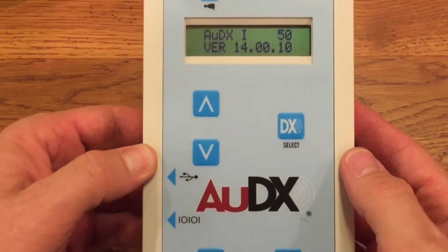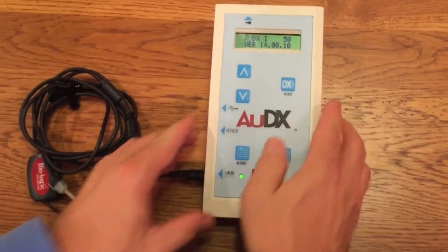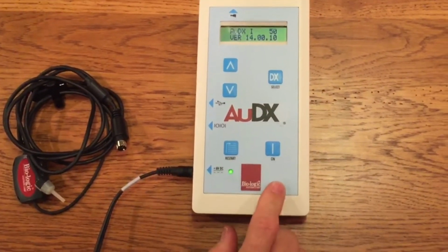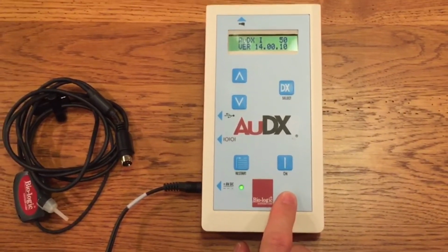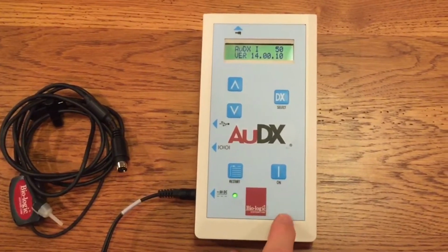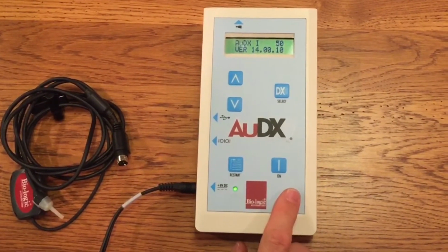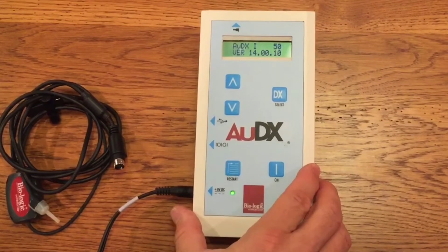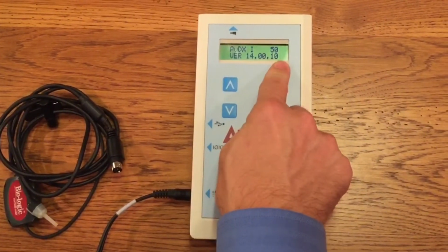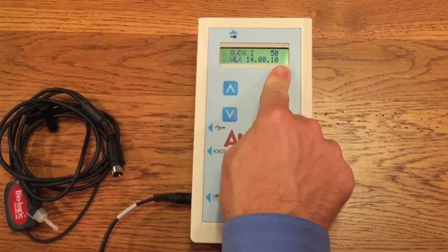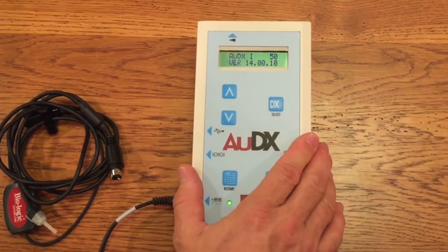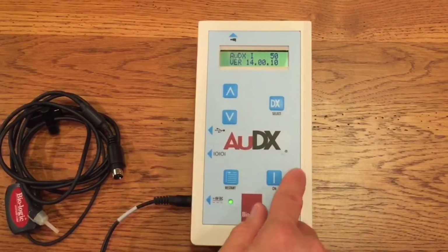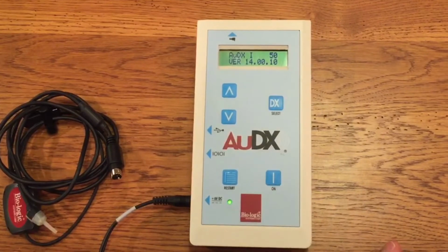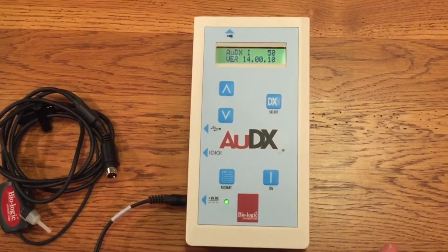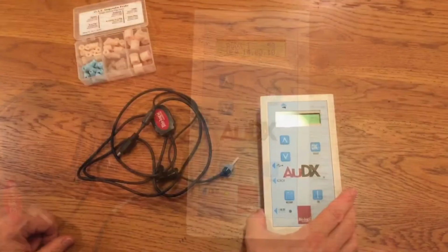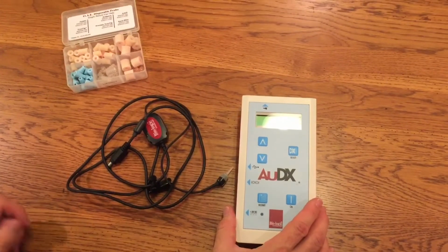Now there's some important things to remember with this particular unit and charging, and I call it the rule of 3. So it takes about 3 hours to fully charge the unit. Once it's fully charged, it will screen for about 3 hours of continuous testing. And then the unit will turn itself off. There is no off button on the unit, so it'll turn itself off after 3 minutes of inactivity. Once the unit is fully charged, then you're ready to screen.